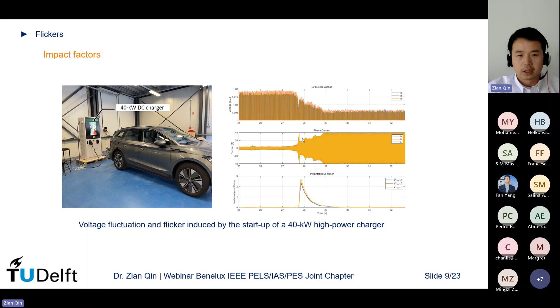And because of this surge current, there is a significant voltage drop induced in the grid voltage. Of course, this single event cannot really create flicker issues. By the way, flicker is also a statistical indicator, right? But imagine that in reality, you may have several chargers in the same network, and charging events start here and there. So eventually, a bunch of these charging start-ups will create flicker issues.